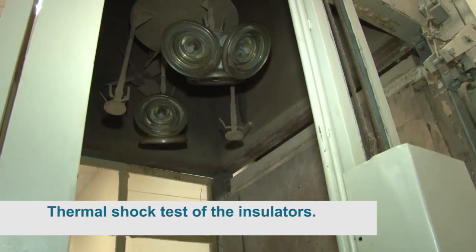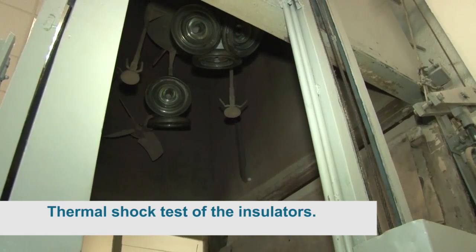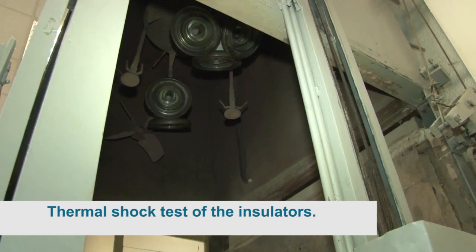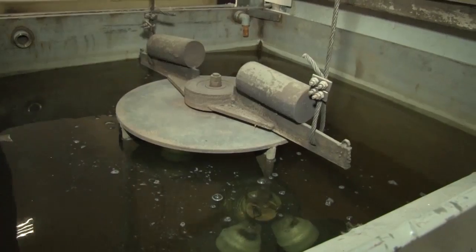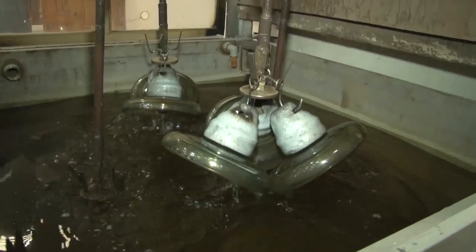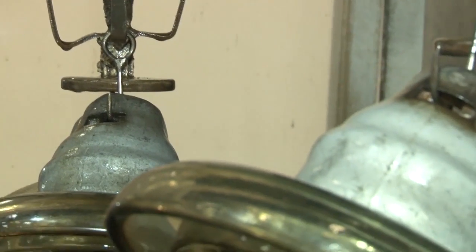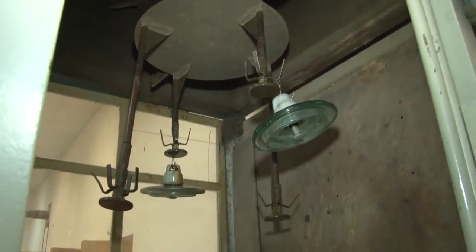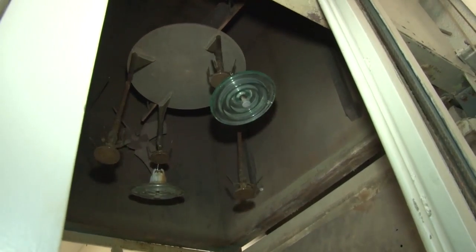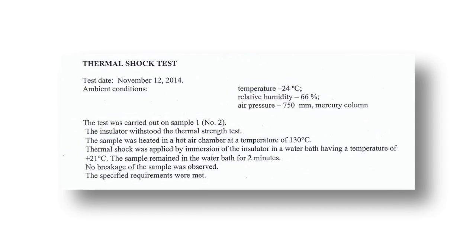Thermal shock test of insulators PS-12A and PS-70E: insulators were placed in a heating oven at 130°C above zero and remained at that temperature for three hours. After that, the insulators were completely submerged into a water bath at +21°C and remained submerged for no less than two minutes. During visual inspection, no cracks or fractures in the cement joint were revealed.